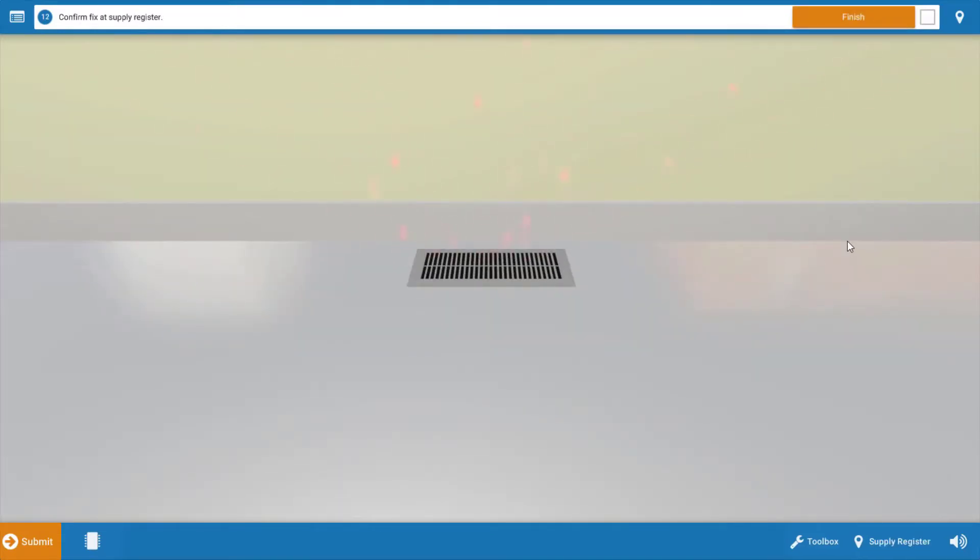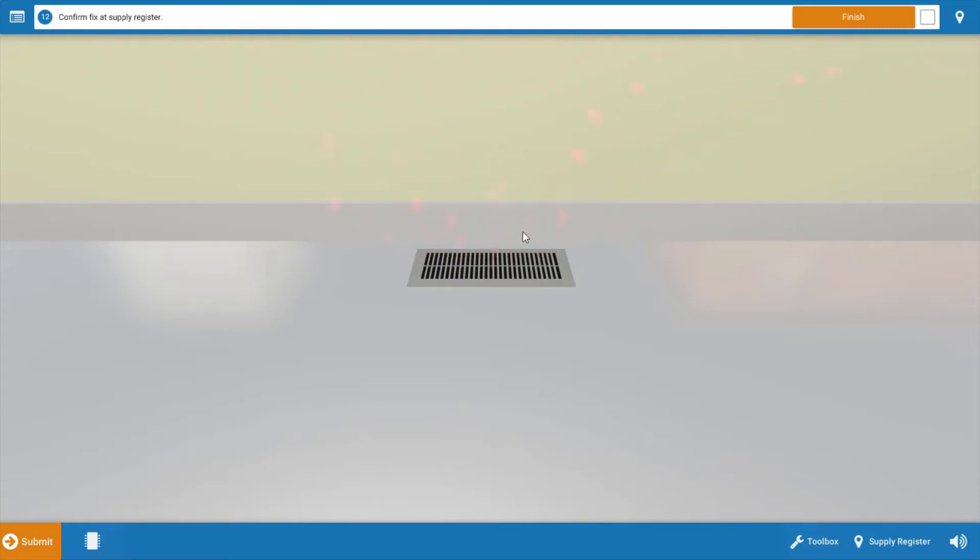Don't forget to observe one full cycle of operation to ensure that everything else is working properly. And also go up to the residence and just verify that heat is being received at the residence. And we can see from the floor register here and this red graphic that we do, in fact, have heat coming into the residence.